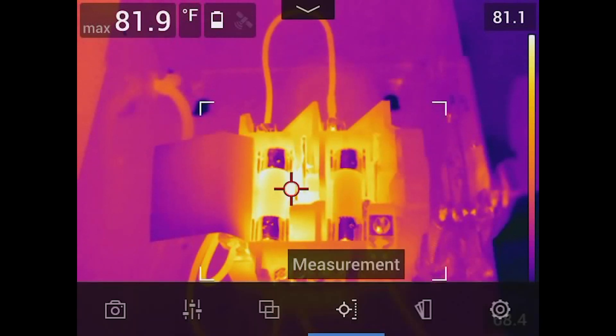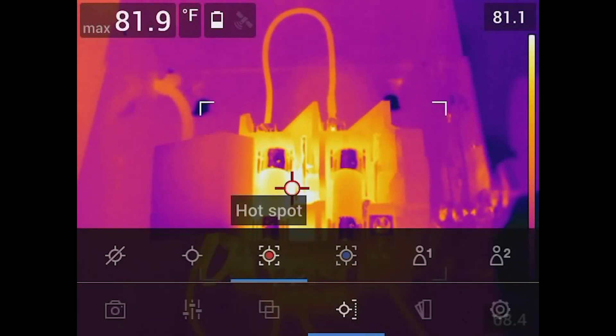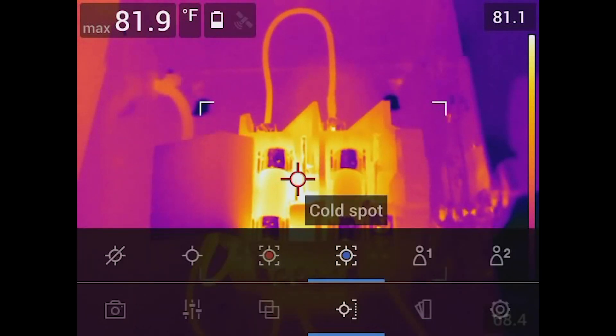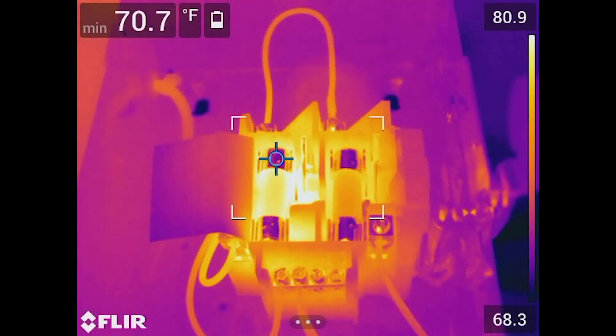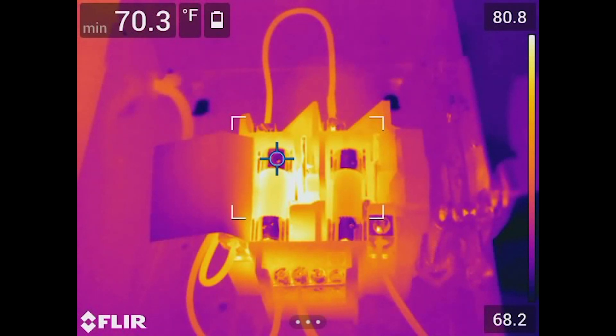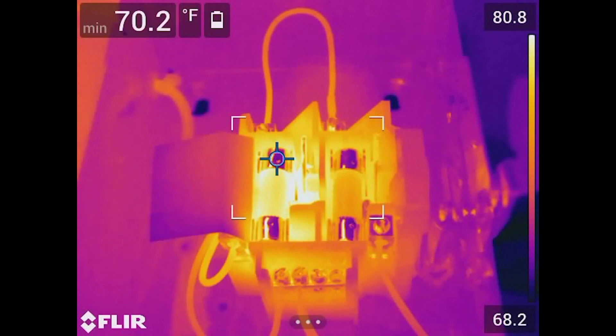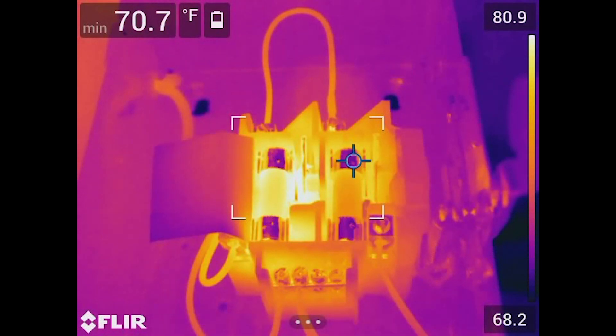Vice versa, if you want to find a cold spot, that's what the blue option is. We can hit cold and it changes from red to blue. The camera has located something on the fuse that's about 70 degrees, which is actually a reflection. As I move my hand around, you can see that reflection coming off the copper and the temperature changes.